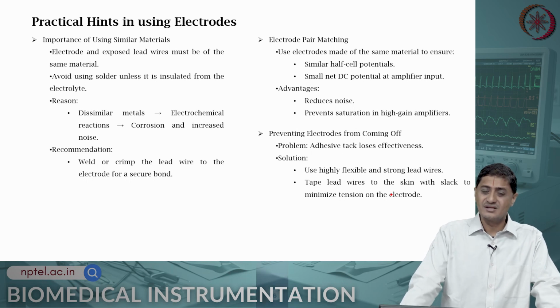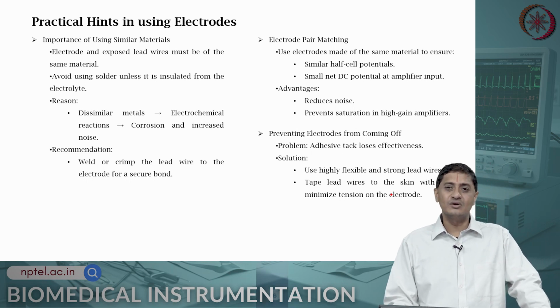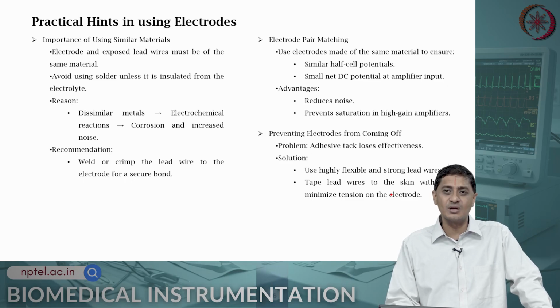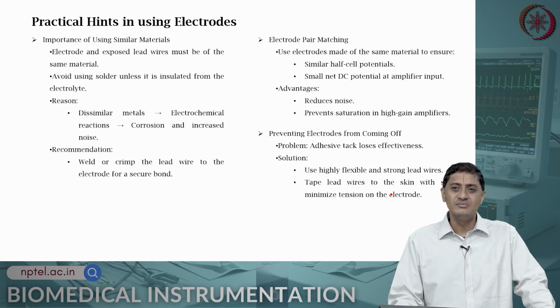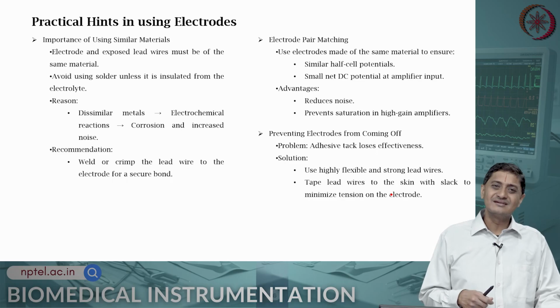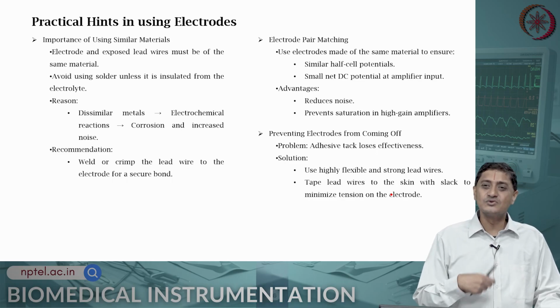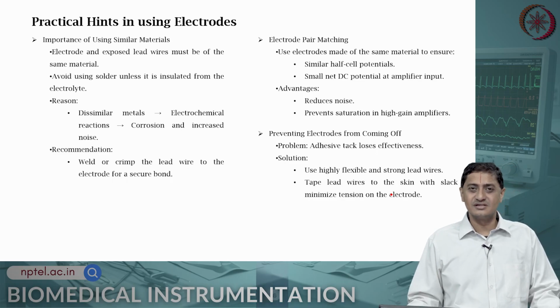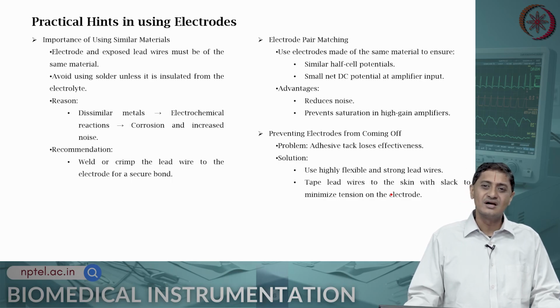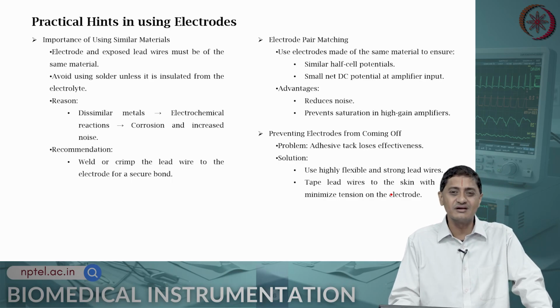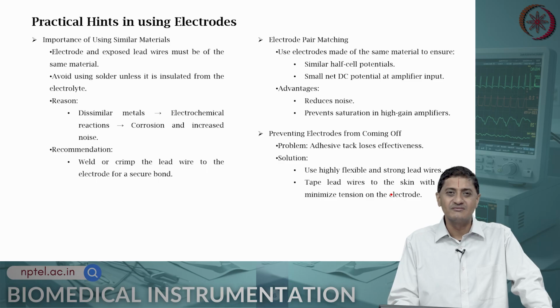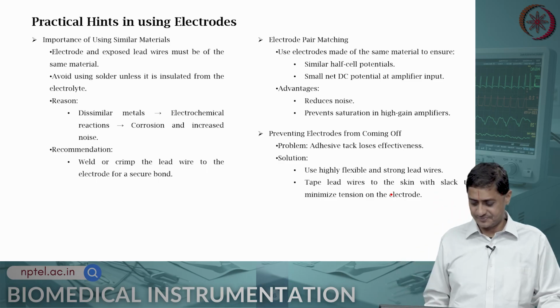And the other is a mechanical problem. You want to make sure that the electrodes do not come off. You have to make sure that there is proper adherence, and the adhesive tack may lose effectiveness. The solution is to use highly flexible and strong lead wires, and you tape these lead wires to the skin with sufficient slack to minimize torsion or bending on the electrode.